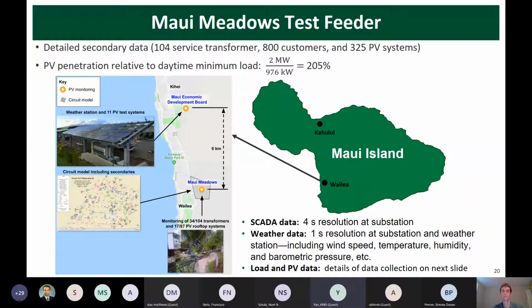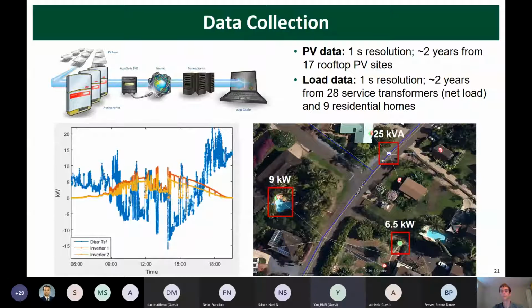In the previous DOE project, we deployed about 60 high-resolution data collection devices to give us visibility at selected service transformers, PV inverters, and customer meters. From the inverter or transformer, data goes to a data accumulator, which is then sent to the server located on our campus. We collect voltage, current, real power, and reactive power, all at very high time resolution in order to capture the variability.